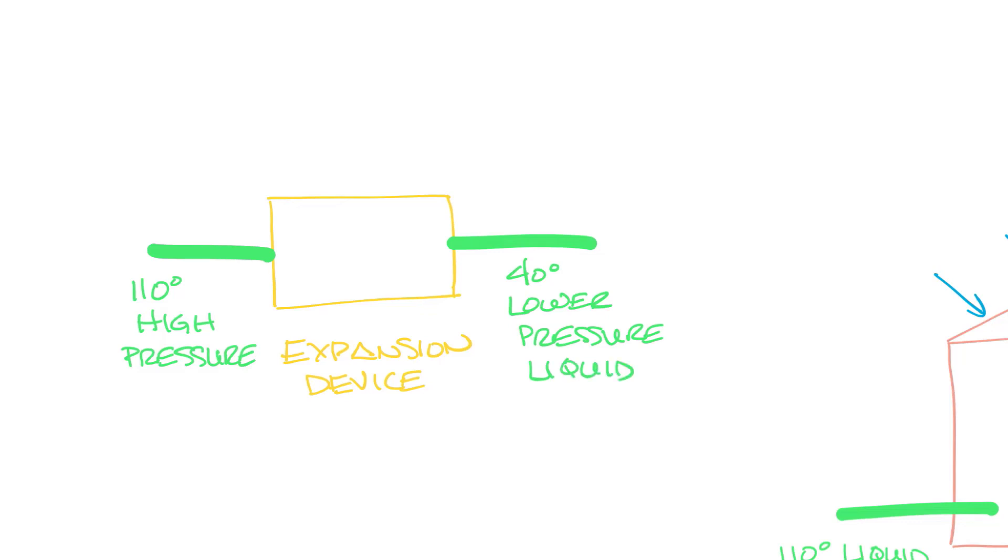So let's draw a little expansion device. And let's draw our refrigeration lines in and out. The expansion device reduces the pressure and temperature of the refrigerant back to where it needs to be to enter the evaporator again. So it's coming in at, say, 110 degree high pressure liquid, goes through the device, and it comes out at 40 degree lower pressure liquid.